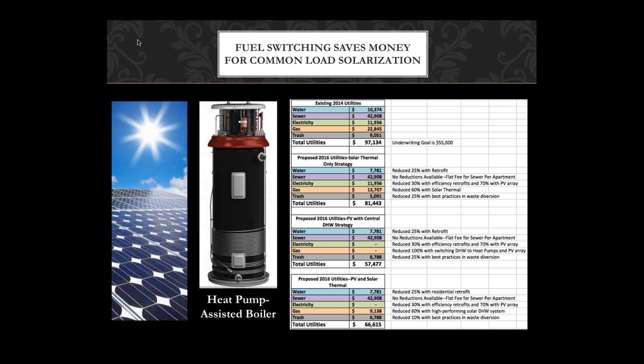We first looked at doing solar thermal offsets, and got the bill down to about $81,000. Then we tried a PV-only offset, which got us down to $57,000, but we had to fuel switch the gas boilers to heat pumps. That's what we did, and that's what's happening right now — there are 12 boilers in there, 11 of them literally brand new, one year old, and they're all getting pulled out and replaced with 80-gallon heat pumps, because that's the financially most sensible thing to do.